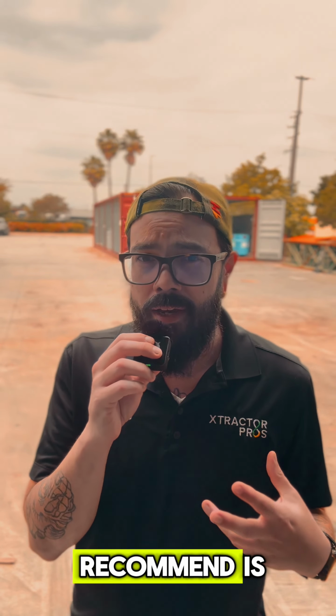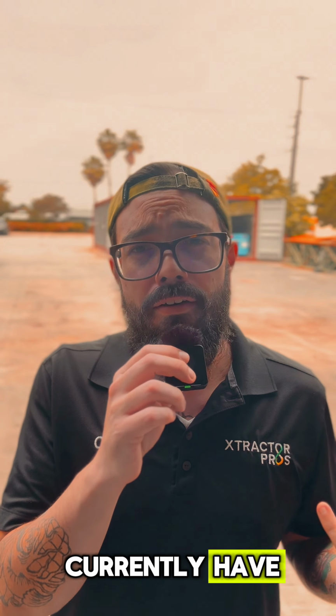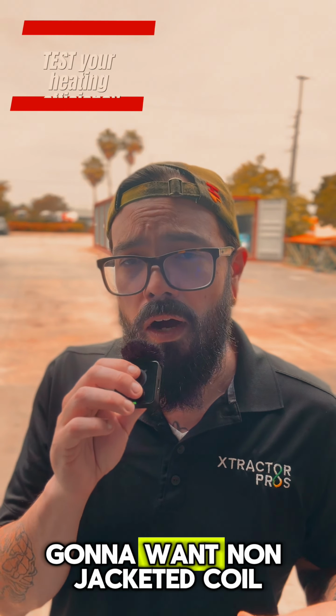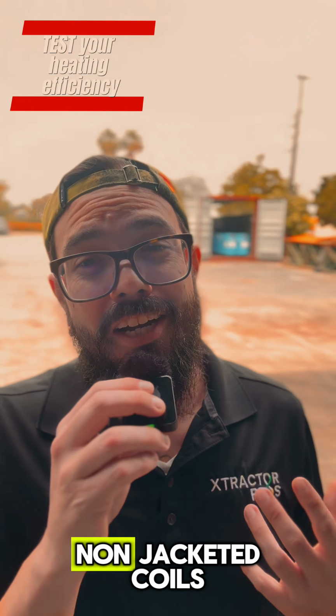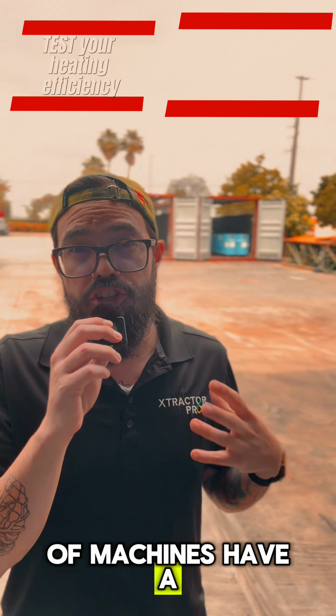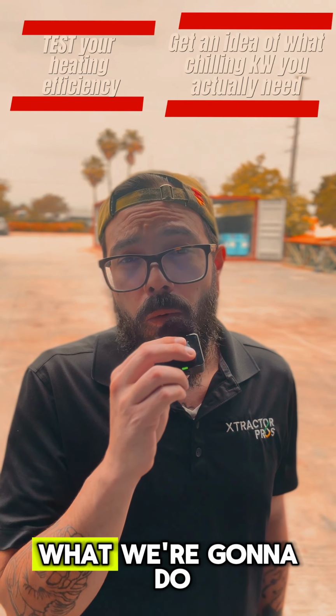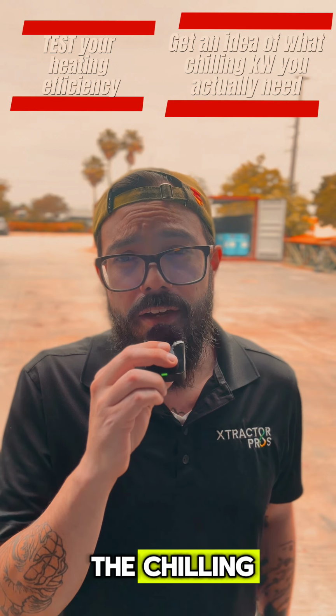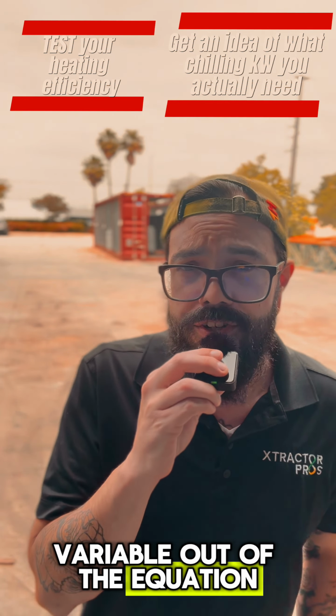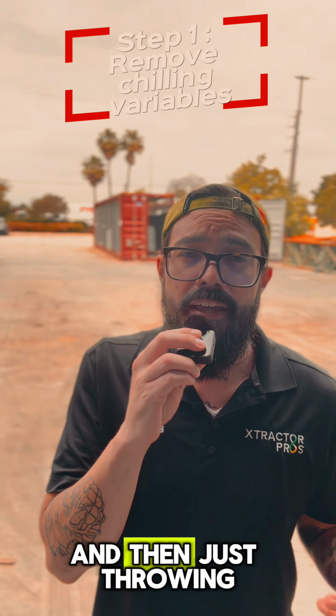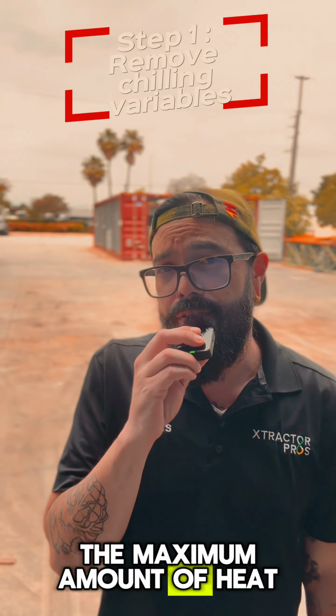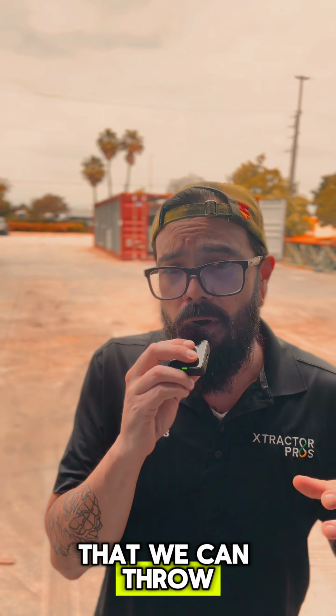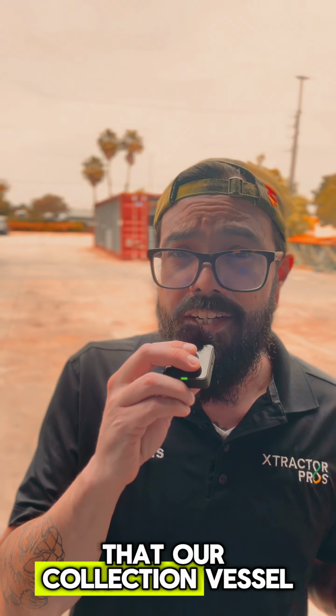So what I'm going to recommend is we disconnect whatever chiller you currently have associated with your machine. You're going to want a non-jacketed coil. I know a lot of machines have a jacketed coil on them. What we're going to do is take the chilling variable out of the equation by replacing it with dry ice and then throwing the maximum amount of heating kilowatts that we can at our collection vessel, to see the average amount of kilowatts our collection vessel is seeing.